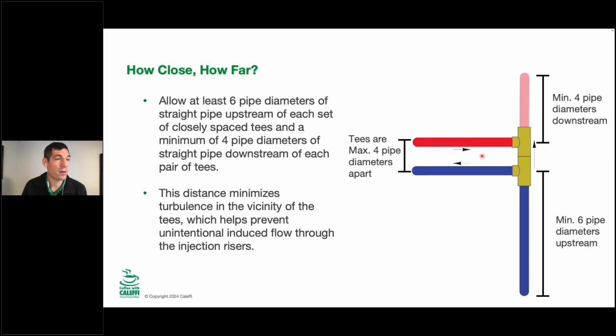If it's 2 pipe diameters apart, that's great. If it's 4 pipe diameters apart, but there's a ball valve in here or something like that, you need to look at the equivalent distance there. So even a full port ball valve, which is just a marketing term, even if it has the exact same inside diameter as the pipe, if this is 1-inch pipe and it's a 1-inch full port ball valve, there is still turbulence there. There is still some restriction, and you're going to have an equivalent foot length penalty there. So in that case, if there were a ball valve right here, it may actually essentially be 8 pipe diameters apart or something like that.